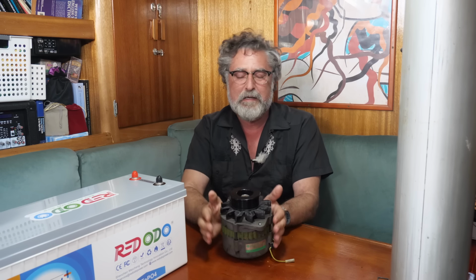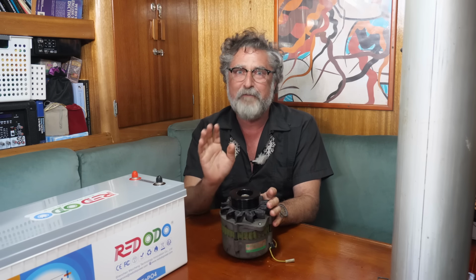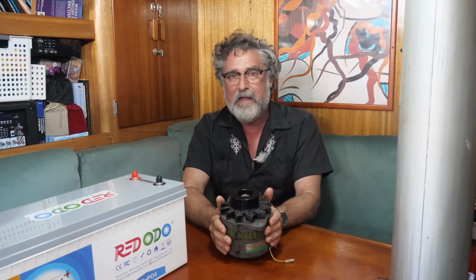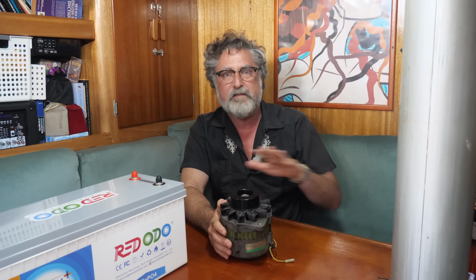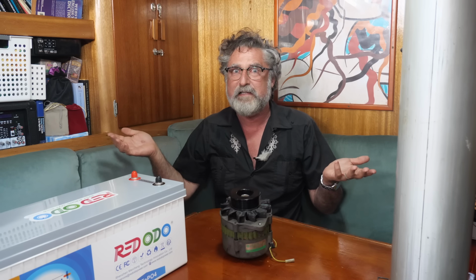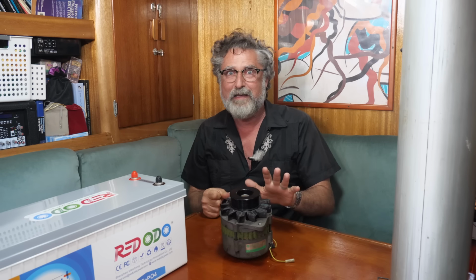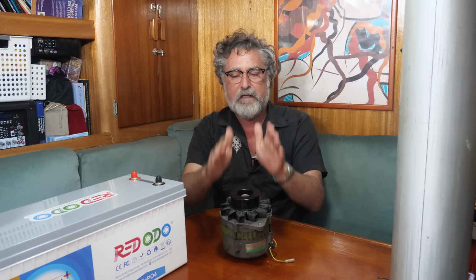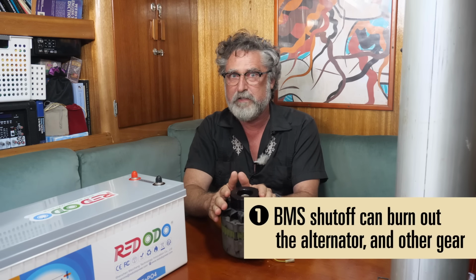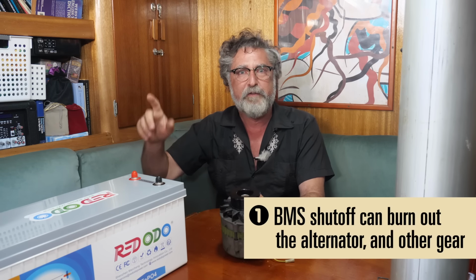But it gets worse, because that is not completely instantaneous. It's like 400 milliseconds. And in those 400 milliseconds, your entire charging system, your entire load system, all your power panels just got exposed to maybe 100 volts DC. I don't know if that new chart plotter you have can handle that. So we've got kind of a two-pronged problem here. When the battery goes away, the voltage skies, destroying the alternator certainly, but very likely doing some other damage.